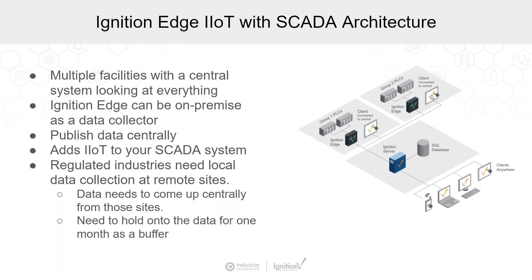Do I have visualization at the sites? I can, if I'm connected up to the central server, but if I lose that connection to the central server, I'm also going to lose my local clients. But because I've got Ignition Edge IIoT, I'm not losing data — I'm still collecting data, and when the connection is restored to the central server, all that data will forward up to the server and backfill our SQL database.